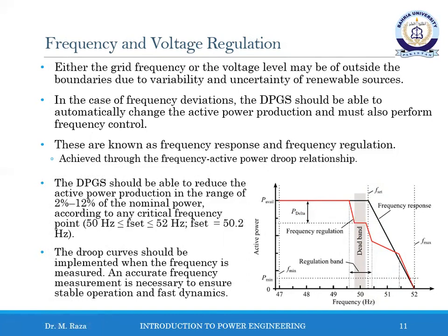Here, the frequency response and frequency regulation profile is shown, where P available is the present available power, P min, such as over here, is the minimum power, P delta is the power difference, F set is the frequency set by the TSO, and F minimum and F maximum are the minimum and maximum distributed grid frequency respectively, such as shown over here, this frequency and that frequency. The generation unit should be able to reduce the active power production in the range of 2% to 12% of the nominal power, according to any critical frequency point. Here, P minimum can reach 0.0 per unit.